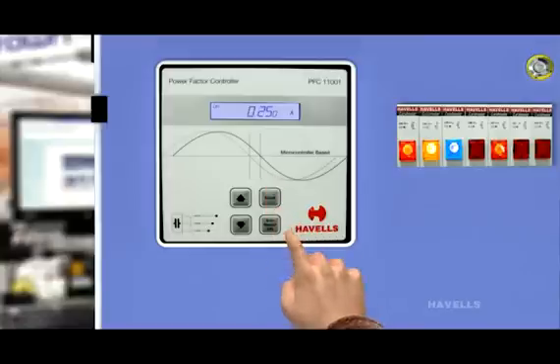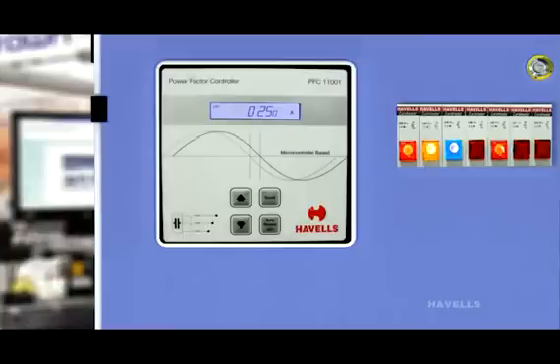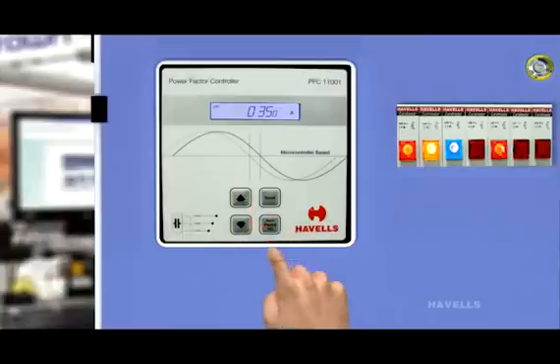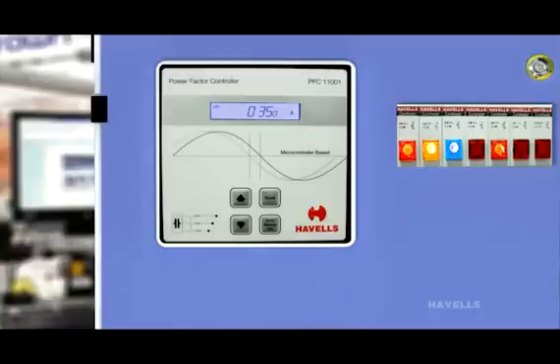Press scroll switch again. Controller shows minimum current on LCD, which is 250 milliampere. Through up and down switch, minimum current can vary from 250 milliampere to 1000 milliampere.